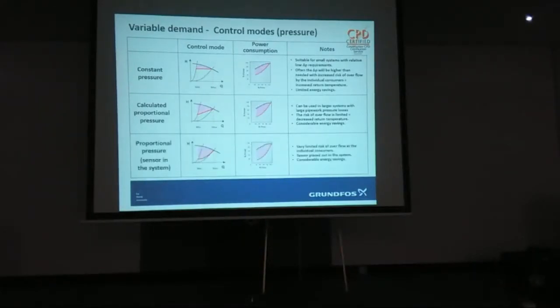This method, by far, is the best method in measuring pressure. The differential pressure transducer or sensor is out in the system somewhere. And that somewhere, CIBSE recommend 2/3 of the way down the line, no problem. But if you've got HIUs, there's only really one in one single building. The best place is the furthest HIU and the longest one away. Now, there's the index. If you've got to maintain 50 kPa up there, that slope, that point down here, virtually no flow, is going to be 50 and a bit kPa.